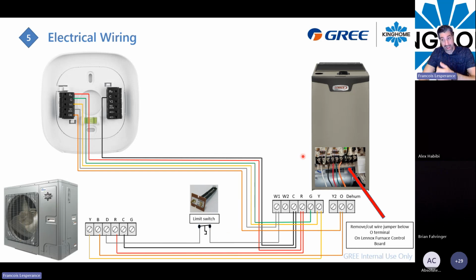Back in the day here in my region, because defrost can take as long as 10 minutes since it's very cold, this limit switch can be installed under the coil, but after the furnace. So somewhere right here. This is why I told you in the beginning, if you have a transition duct between the coil and the furnace, you will just have to drill a hole in your transition and put that limit switch directly right there.